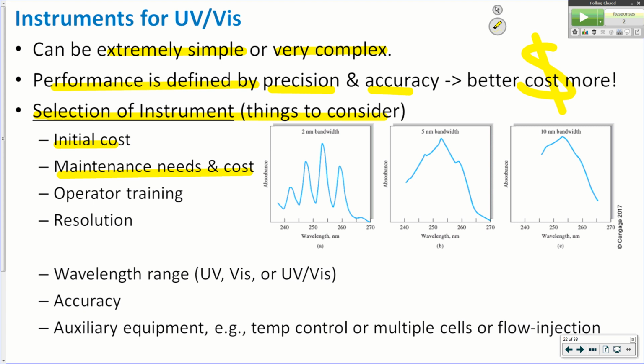If it's an instrument that's on 24 hours a day, even though you may pay $12,000 to $14,000 for something to acquire UV spectra, we have to realize that a UV lamp is going to cost anywhere from $1,000 to $2,000 to replace, and it has a 1,000-hour operating life, and then after 1,000 hours you've got to replace it.